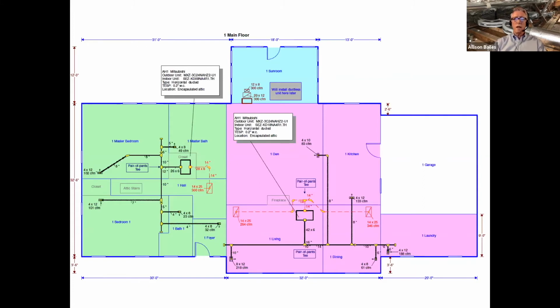There are two low static duct systems in the attic. So here's one for the bedroom side of the house, and that's a fair amount of duct work over there. One return, and then a bunch of supplies with a trunk line. The main part of the house over here has a bigger air handler, same rated for same static pressure. It's a Mitsubishi SEZ unit, and rated for 0.2 inch of water column static pressure, which is pretty low. Standard air handlers are rated for 0.5 or 0.6. So 0.2 is really low, which means you have to have a really good duct system to make it work.